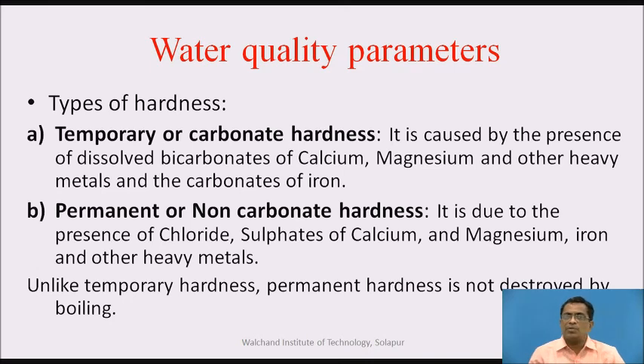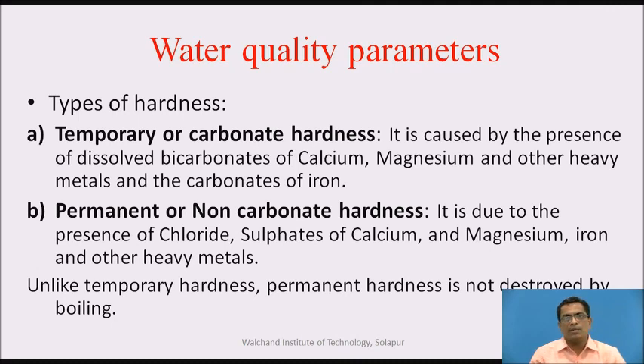Types of hardness: basically there are two types of hardness in water — temporary and permanent. Temporary or carbonate hardness is caused by the presence of dissolved bicarbonates of calcium, magnesium, and other heavy metals, and the carbonates of iron. Permanent hardness is due to the presence of chlorides and sulfates of calcium, magnesium, and other heavy metals. Unlike temporary hardness, permanent hardness is not destroyed by boiling.